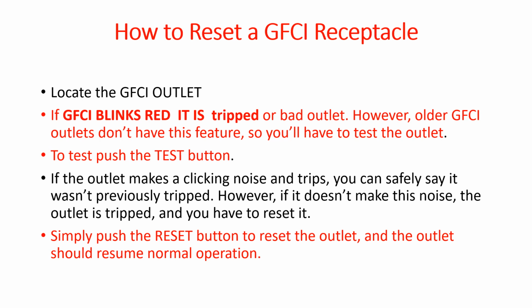Now, how to reset a GFCI receptacle? You will see there are two buttons. If the GFCI receptacle blinks red, then it means that it has tripped, and you will have to check. You can test it also by pushing the test button. If the outlet makes a clicking sound and trips, you can safely say it wasn't previously tripped. However, if it does not make the noise, the outlet is tripped already and you have to reset it.